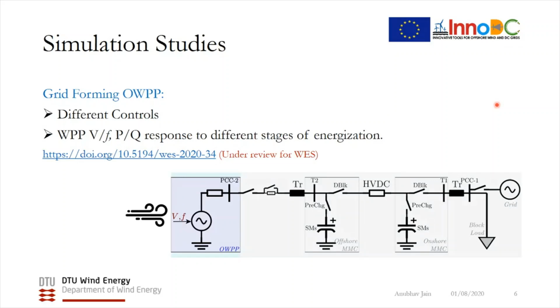Some of the studies that we have performed are first to look at different grid forming controls and how the offshore wind power plant voltage responds to the different transients of the different stages. So the offshore energization, the DC link energization, and then the onshore PCC energization, and how the voltage and frequency transients and the real and reactive power transients look for these different stages. And the results have been summarized in this article, which is under review for Wind Energy Science.